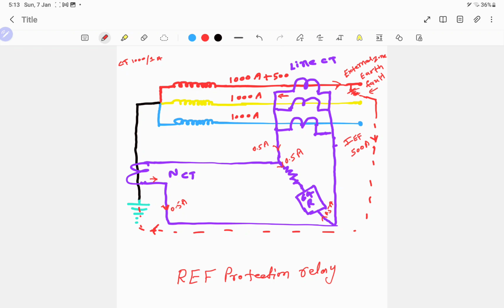Now this relay is used to protect the inner zone of the transformer winding. So assume there is a fault outside of the protection zone. From here to here, this is the inner zone, and outside of the CT is the outer zone. So it will not protect the outside zone. Now we will see how it works.